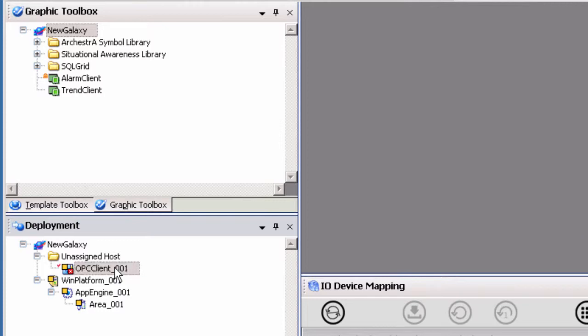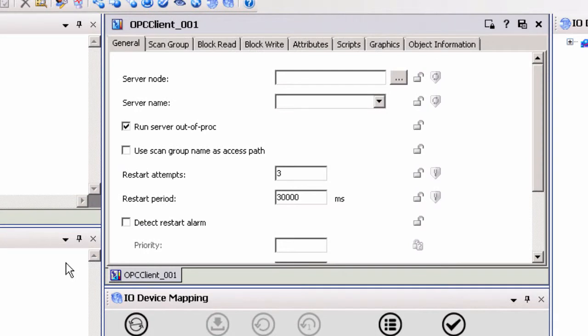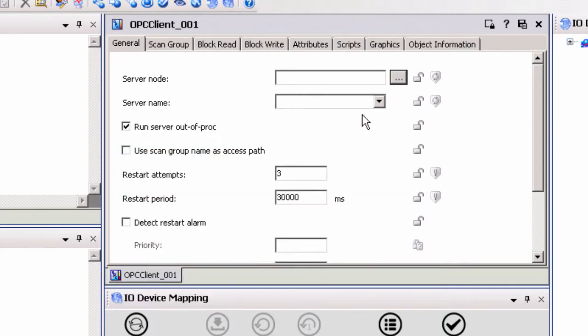Double-click the OPC client object under the unassigned host to open the object properties to the right of the template toolbox. If TopServer and System Platform are located on the same PC, leave the server node blank. If not, click on the ellipses button to the right of the server node text field to open the browse node dialog box. Select the domain of the computer node where TopServer is installed to display a list of available nodes. Highlight the appropriate node name and select OK.